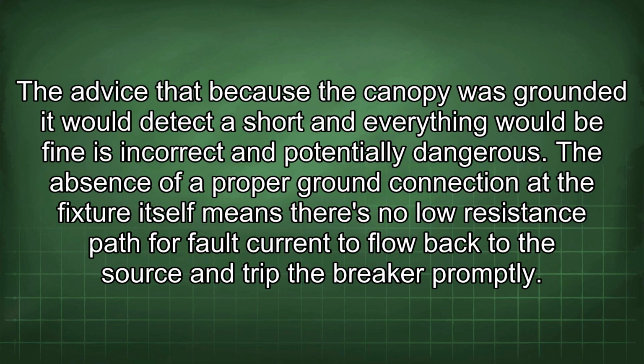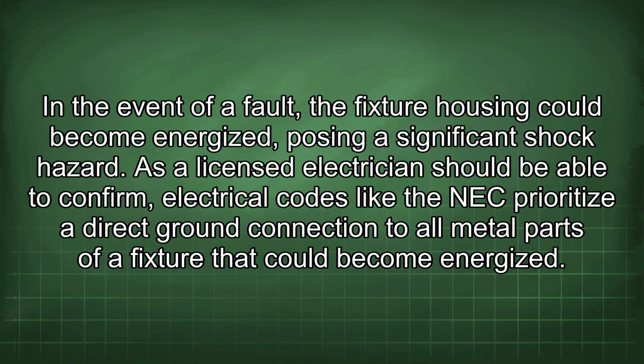The advice that because the canopy was grounded it would detect a short and everything would be fine is incorrect and potentially dangerous. The absence of a proper ground connection at the fixture itself means there's no low resistance path for fault current to flow back to the source and trip the breaker promptly. In the event of a fault, the fixture housing could become energized, posing a significant shock hazard.